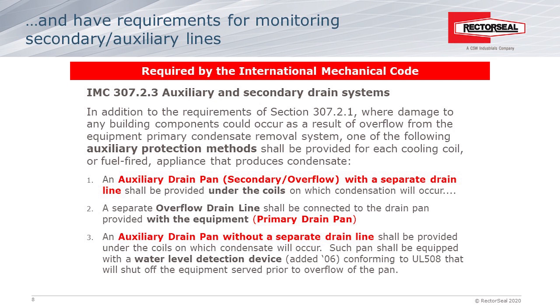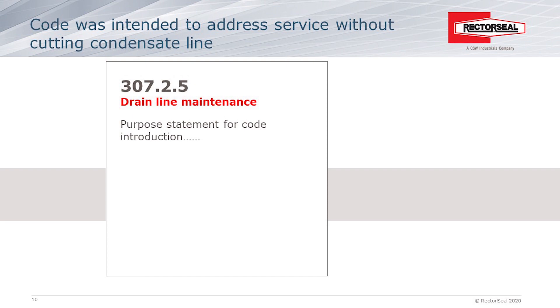Both methods three and four notify the building occupants that a blockage has occurred because the cooling system will cease to function. The exception recognizes that some fuel-fired appliances that produce condensate will have a built-in method of shutting down when a blockage occurs. The IMC commentary was recently updated and will be available in the 2021 edition, which elaborates a lot more on the importance of proper maintenance and what is behind the intent of this code section.